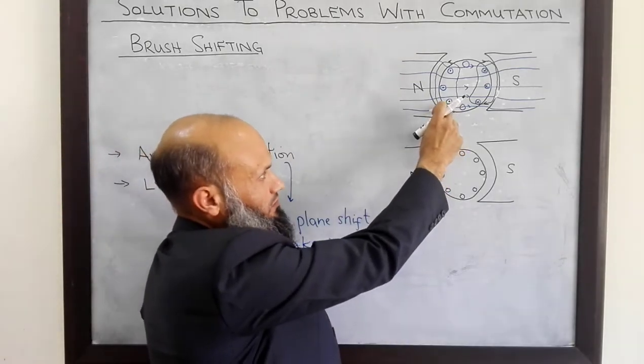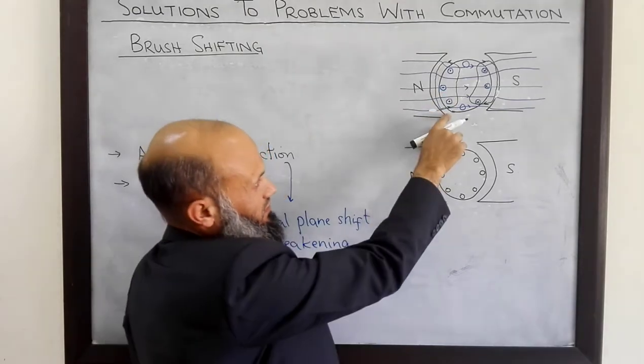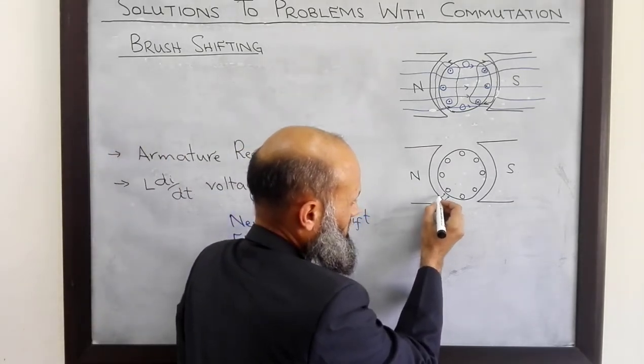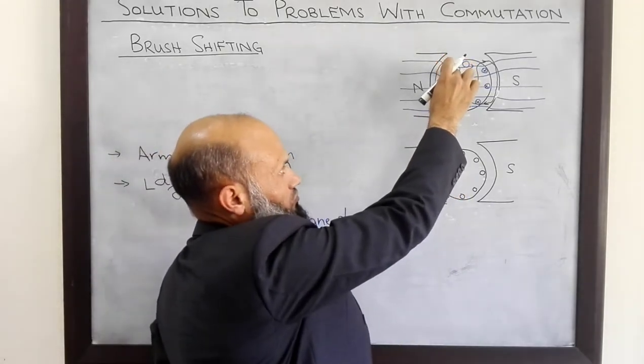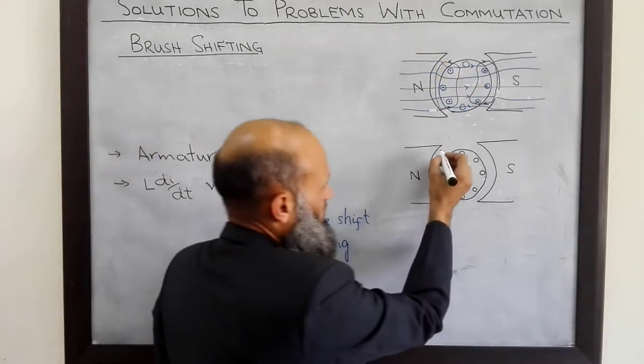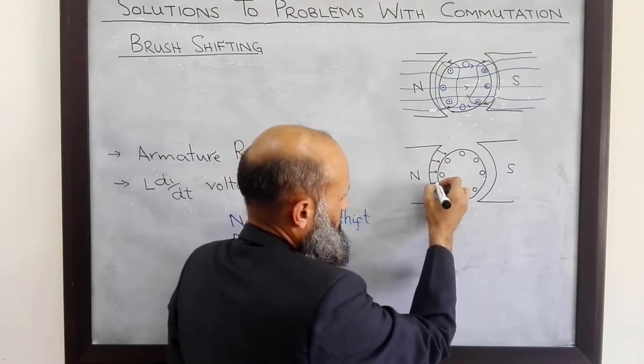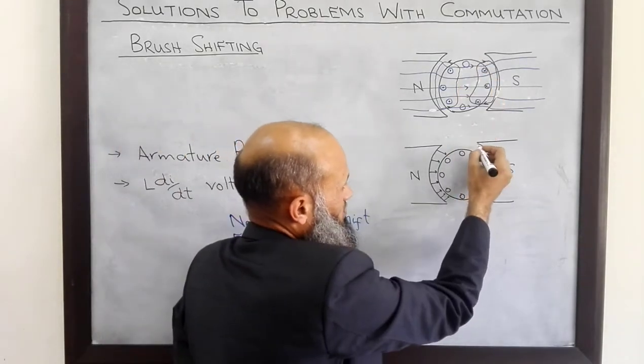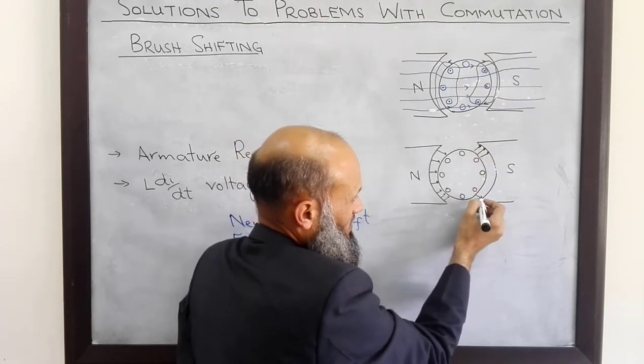At this end of the pole, the MMF due to current in these conductors and MMF of the main poles are in the same direction, so flux density at this end of the pole increases. At the other end of the pole, the MMF due to current in these coils and MMF due to the poles are in opposite directions, therefore flux density decreases at that end. The same applies at the other pole: flux density increases at one end and decreases at the other.